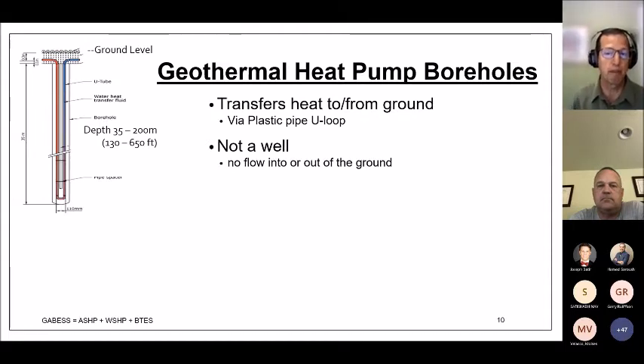A geothermal heat pump borehole is a drilled hole in the ground with a loop of plastic pipe in it, and that loop is grouted into the ground. So it is not a well; there's no flow into or out of the ground formation. The only flow is through the plastic pipes, completely self-contained, and then it's conductive heat transfer out into the formation that the hole is drilled in, where the plastic pipe is.